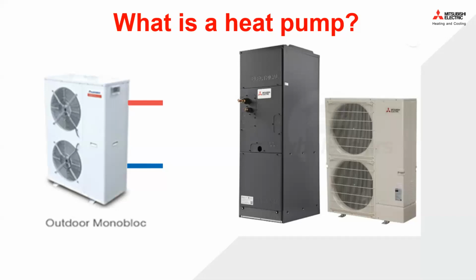Now heat pumps can come in different formats. On the left there, we have a monoblock system where all the components are contained inside that box, and then you just run water. So you have a heat exchanger that will exchange the heat from the refrigerant to the water, and that would run into the space. And then we have our split systems, which everybody knows as mini splits, but if you have an air handler, it's not quite mini. And if you have a large capacity unit, this is a very large outdoor unit. But this is what we consider mini splits, a two-part system: an inside component, an outdoor component, and refrigerant lines connecting the two.